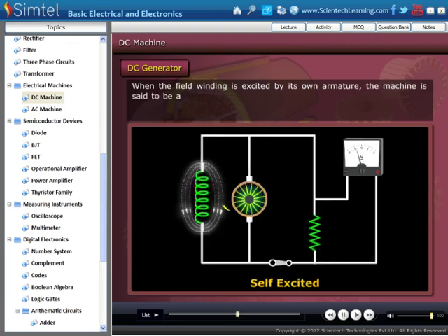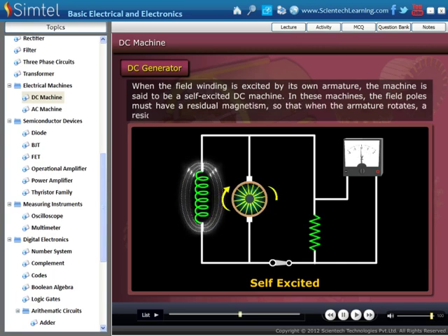Now when the field winding is excited by its own armature, the machine is said to be a self-excited DC machine. In these machines, the field poles must have a residual magnetism so that when the armature rotates, a residual voltage appears across the brushes. This residual voltage should establish a current in the field winding so as to reinforce the residual flux. A self-excited DC machine can be subdivided as follows.